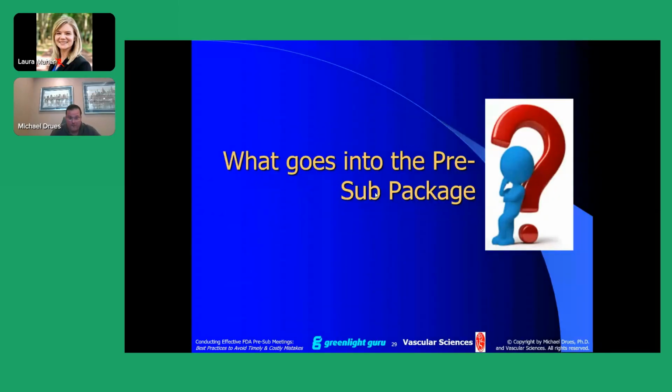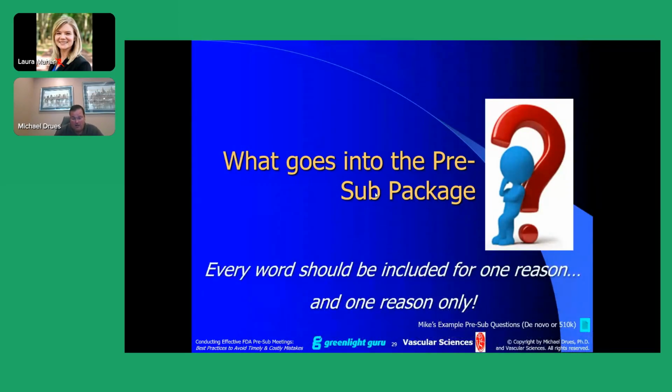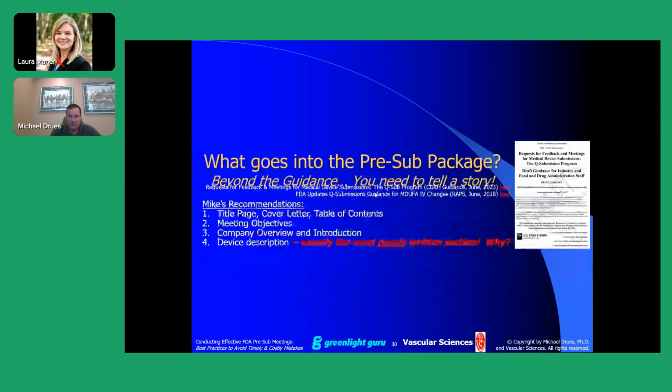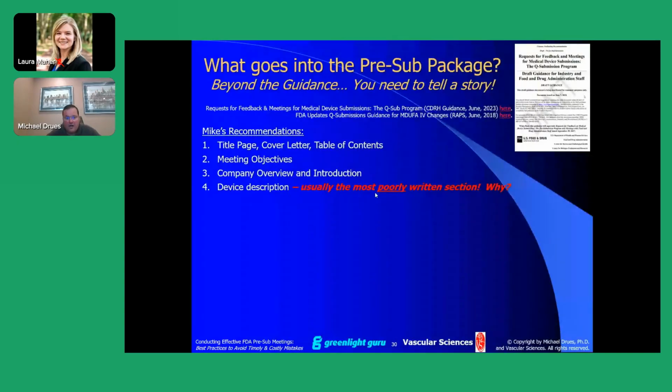So what goes into the pre-sub package? As I said before, every word, every punctuation mark should be put in there for one reason and one reason only, and that is to help FDA come to the answer to the question that you want them to come to. So here is, beyond the guidance, some of the suggestions of what you should put into your pre-sub package. Obviously, title page, cover letter, table of contents, your meeting objectives. I'll talk more about those in a moment. That's probably the most important part of the entire pre-sub process: the meeting objectives and the pre-sub questions.